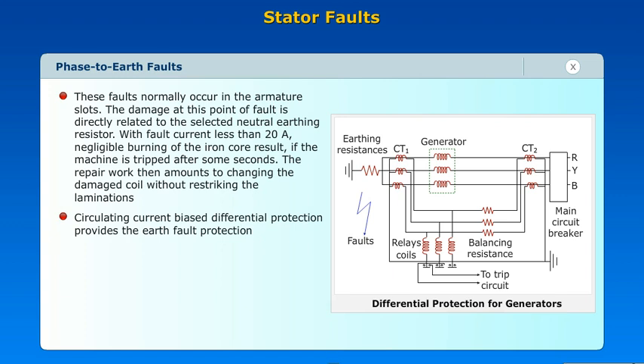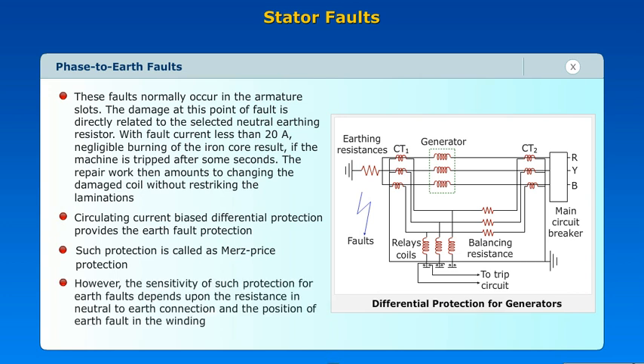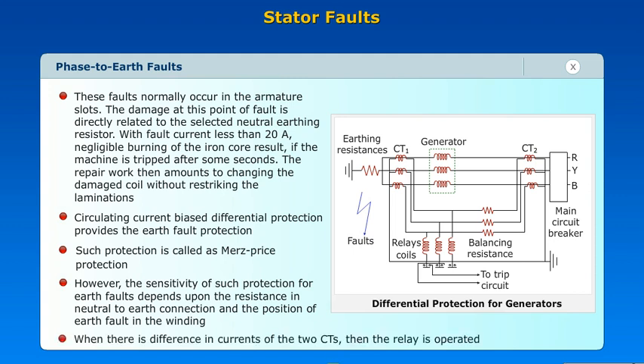Circulating current biased differential protection provides the earth fault protection. Such protection is called Merz Price protection. However, the sensitivity of such protection for earth faults depends upon the resistance in the neutral-to-earth connection and the position of the earth fault in the winding. When there is a difference in currents of the two CTs, the relay is operated.